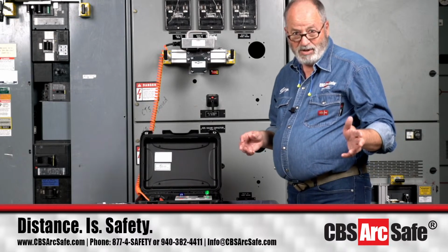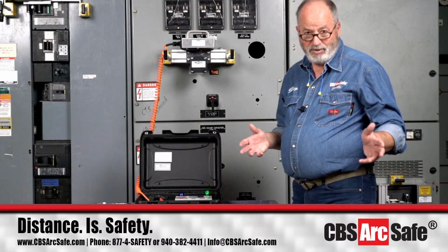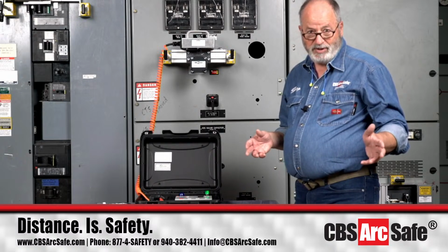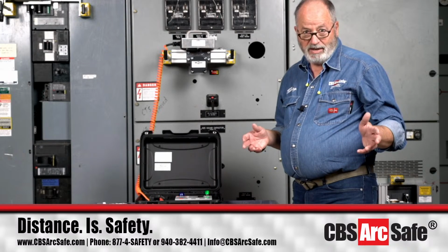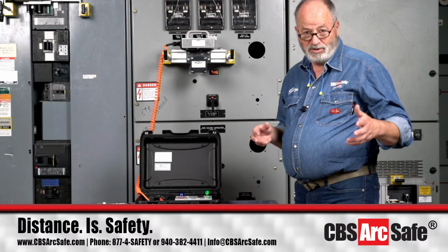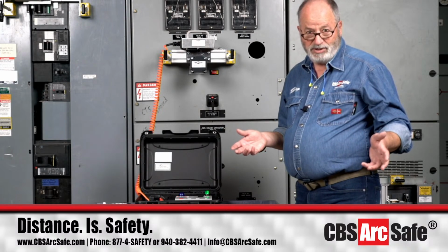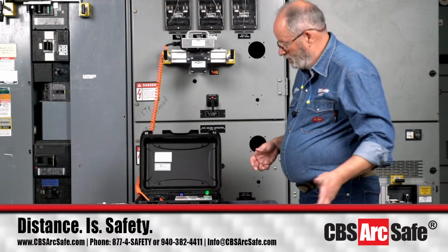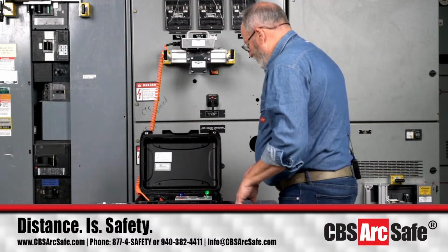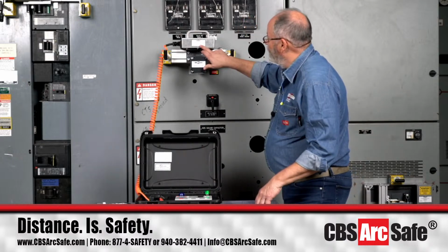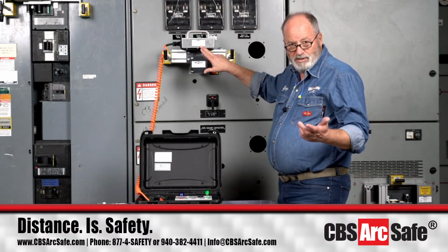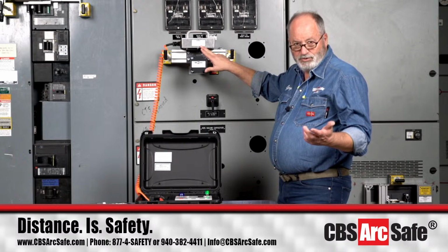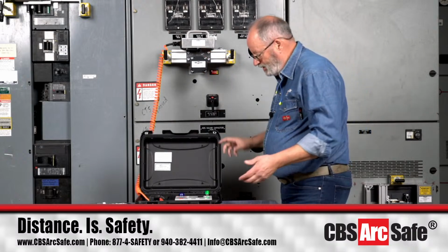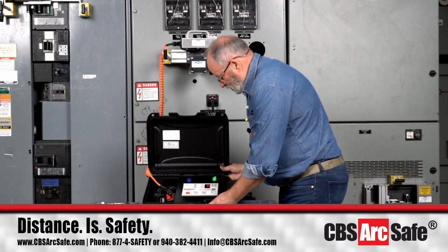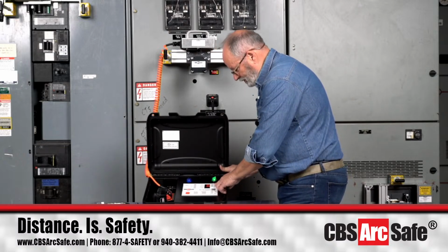That being said, we've worked to develop these torque numbers ourselves for these breakers, based on experience using torque wrenches and measuring running torque values, so we can avoid damaging switchgear during the racking process. We had to develop this information ourselves. Install is 4.5, since it usually takes more torque to get a breaker in than to get it out, which makes sense. So we'll set 4.5 here for install.